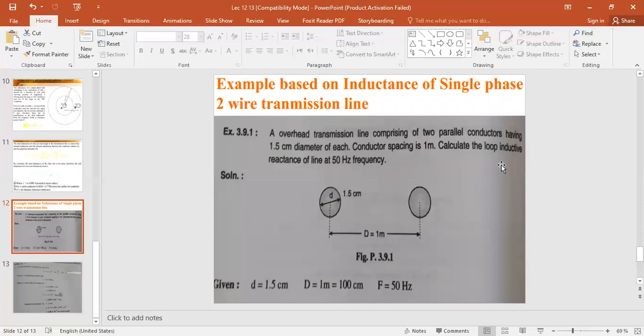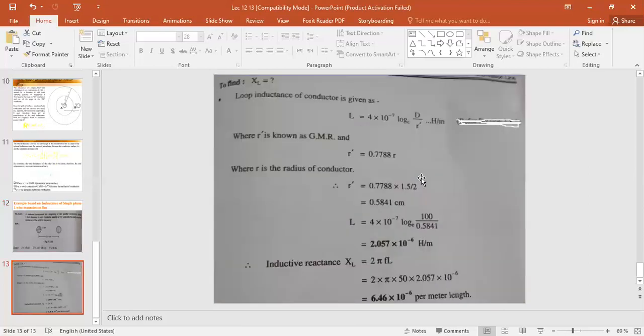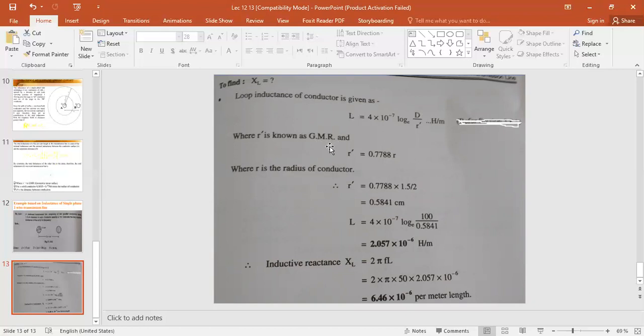We need to find the loop inductive reactance. The formula for loop inductance is: L = 4 × 10⁻⁷ × log(D / r'), where r' is known as the GMR — the Geometric Mean Radius.